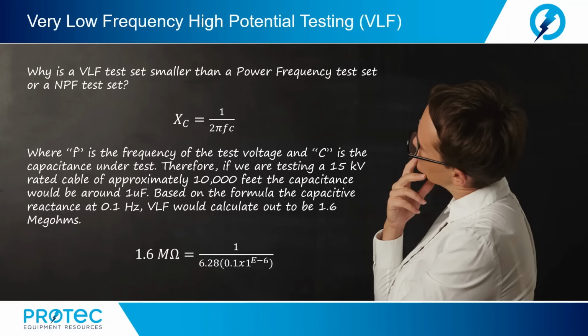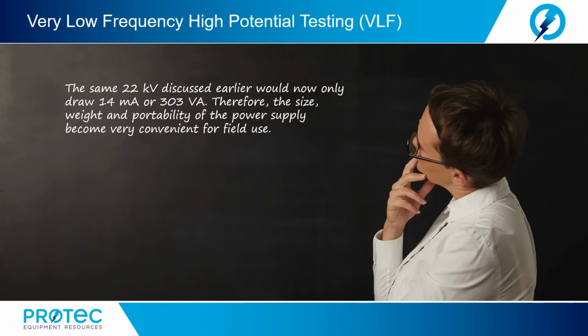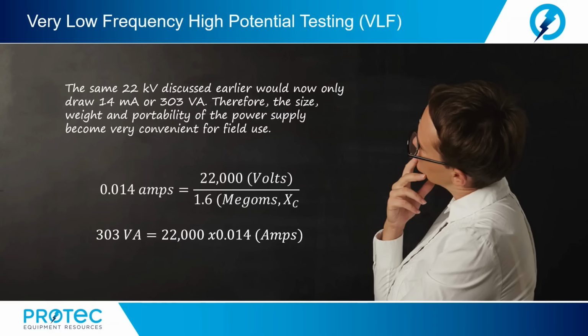So again, to calculate what we would need in our power supply, we want to energize to 22,000 volts, as discussed earlier. But now we are only going to draw 303 VA. Again, 22,000 volts divided by the 1.6 megohms of capacitive reactance would give us 14 milliamps. To find the VA requirement of our voltage source, 22,000 times the 14 milliamps, 303 VA. Obviously, this test set has become much smaller, more portable, and easier to use in a field testing application.